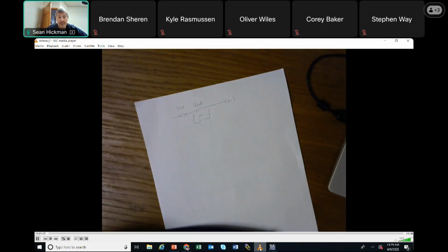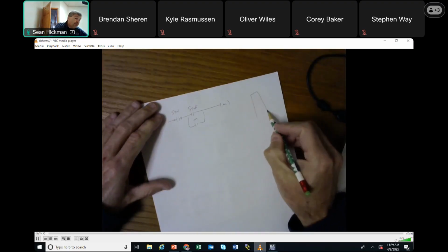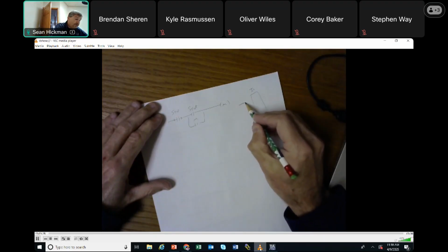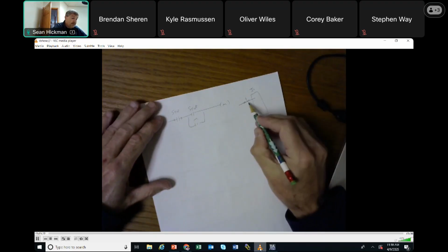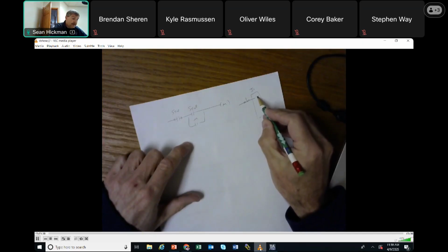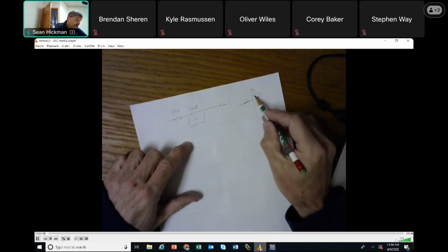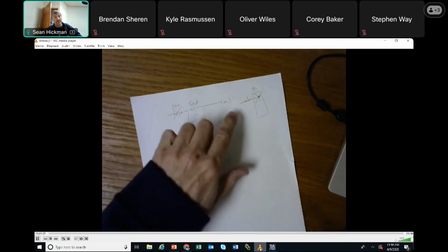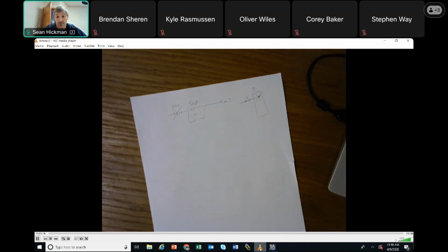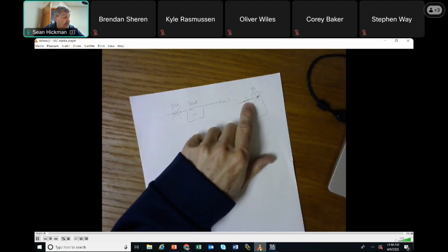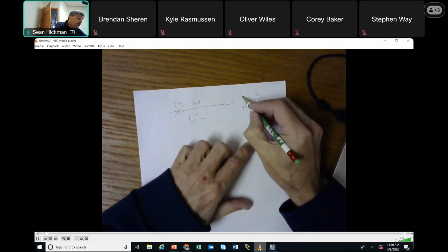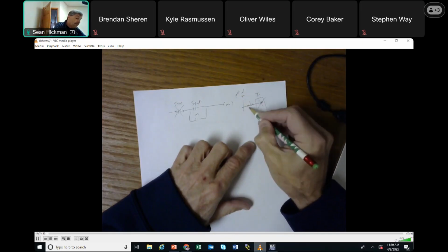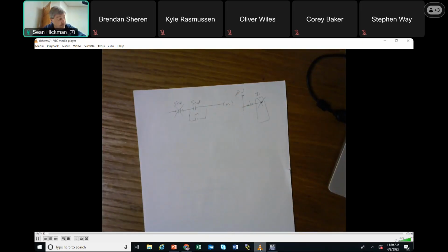So if you kill the MCR, then on your input module, where you have the closed push button, you'd be getting a light on here automatically because it's closed. But if you kill the power to it, that light goes off, this goes off, and it would kill your memory. So that's another beauty about having your stop normally closed, because if the MCR dies, then it's going to bring down your system bit.